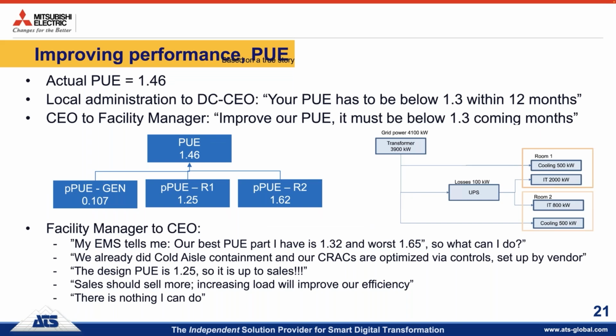So again, this is based on a true story about improving PUE. There's a data center with a PUE of 1.46. The local administration told the data center CEO that the PUE has to be below 1.3 within 12 months, as that's the regulation in the area, and at 1.46 they're not compliant. So the CEO went to the facility manager and said, you have to improve our PUE to below 1.3 - that's your task for the coming months. Looking at the drawing, this data center has two data rooms using a total of 4 megawatts, and the PUE is 1.46.